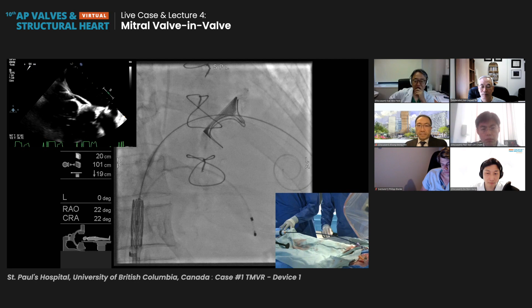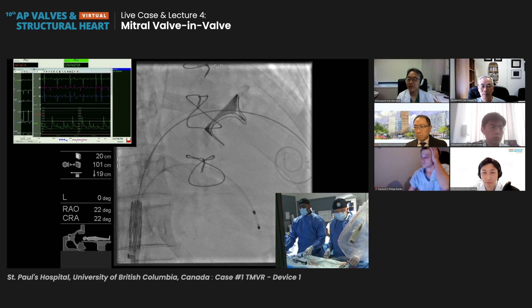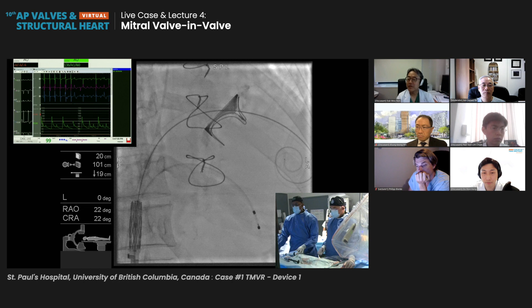Good. Okay. Do you want to test the pacer at this point, John? Yeah, this is a good time to test the pacer. Can you guys take care of that? Okay, so we're hooked up. So we're going to test at 100, output of 20, sensitivity of 3, and backup heart rate of 40. So we're going to test with the tester part. So pacer ready? Pacer on. Okay, it's capturing. Put the rate up to 120, please. Okay, that's right. Good. You can stop pacing.